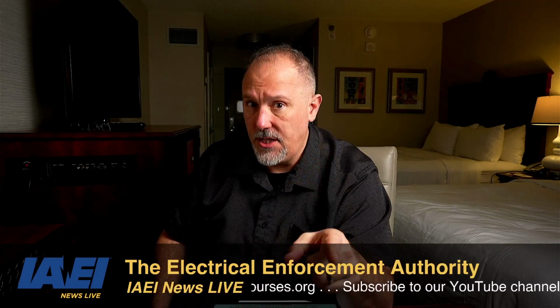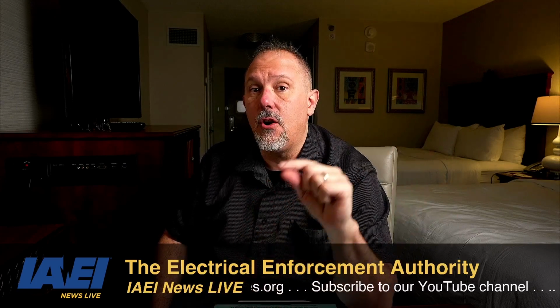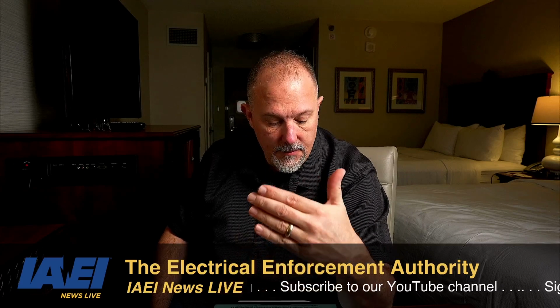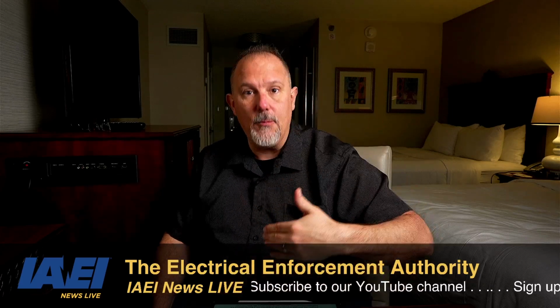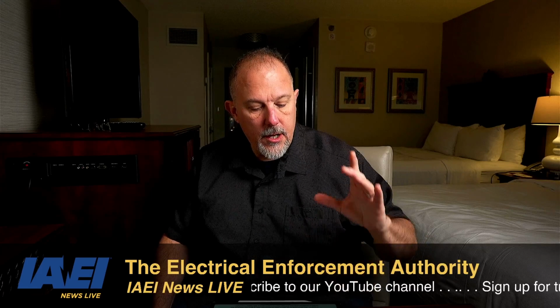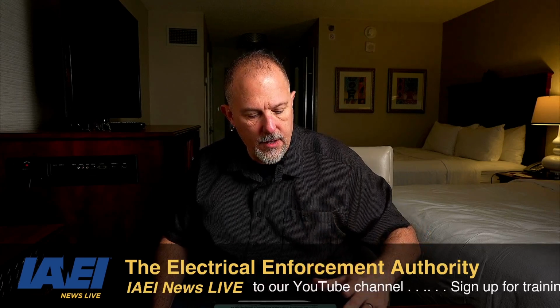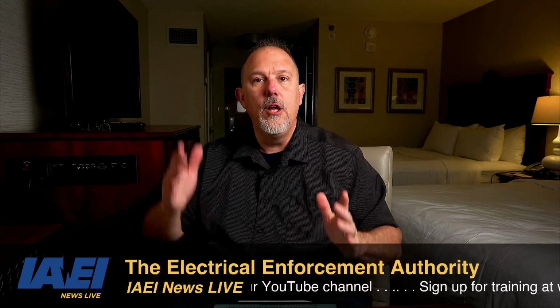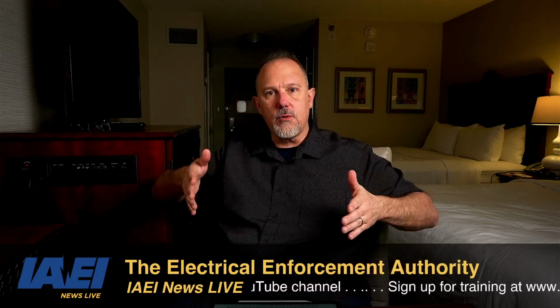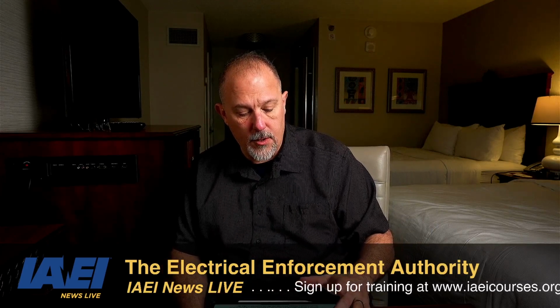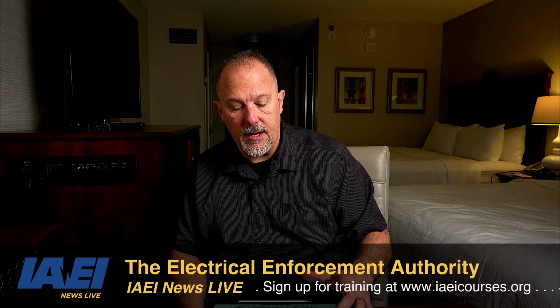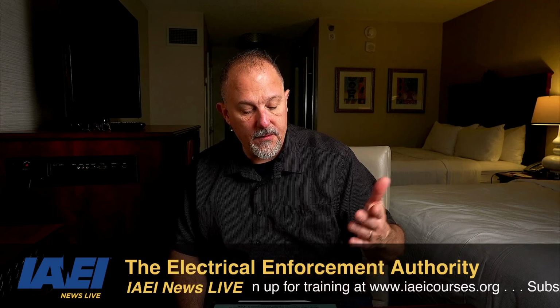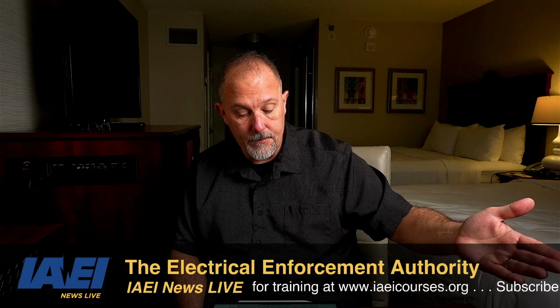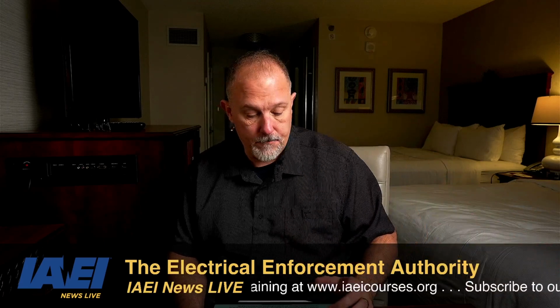What about energy storage? So we have an emergency disconnect on energy storage systems. And then we said, what about generators? And now we have a requirement for emergency shutdown of the prime mover in 445.19. So all of the sources of power for first responders can be turned off. Remote emergency shutdown for other than one and two family dwelling units, generators with greater than 15 kW rating shall be provided with a remote emergency stop to shut down the prime mover.